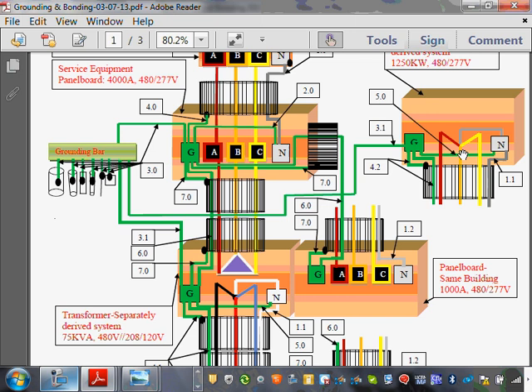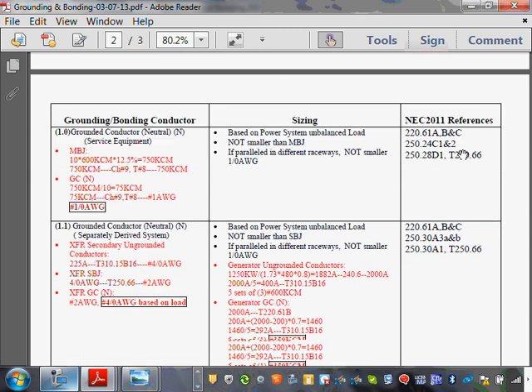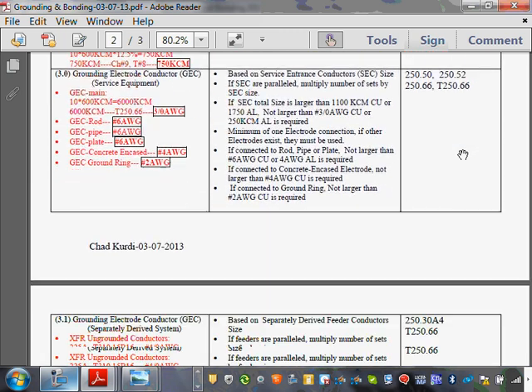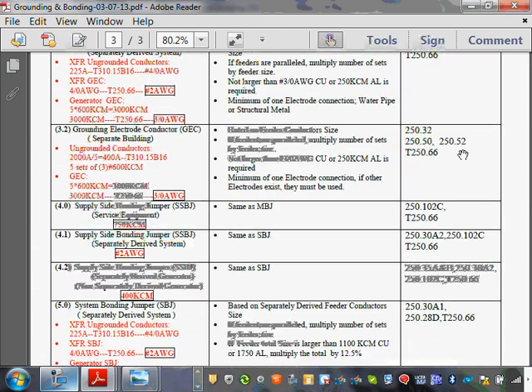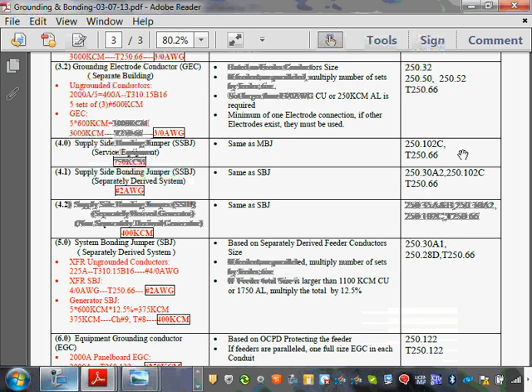Then you have to tie your newly created neutral, that you own and operate at the same voltage, 277, to the grounding electrode system, bond it together. It's called the system bonding jumper, exactly like at the transformer. So let's go to 250.30 and get my system bonding jumper. I want you to focus only at the bottom here. It says generator system bonding jumper. Can you guys see that?